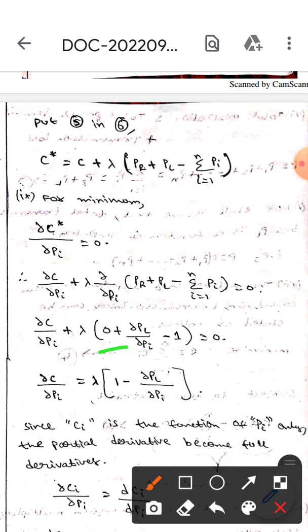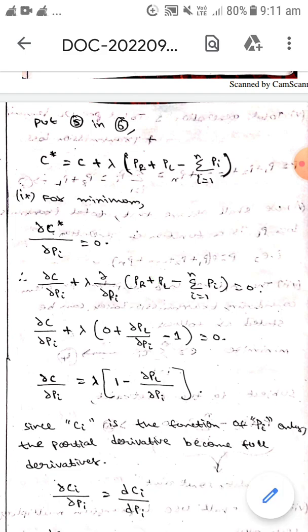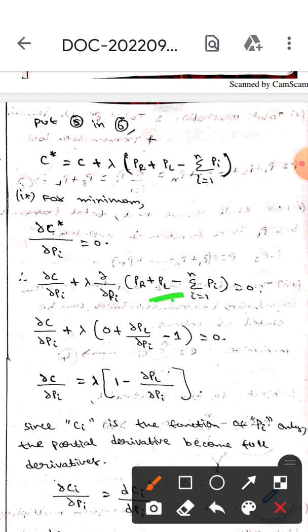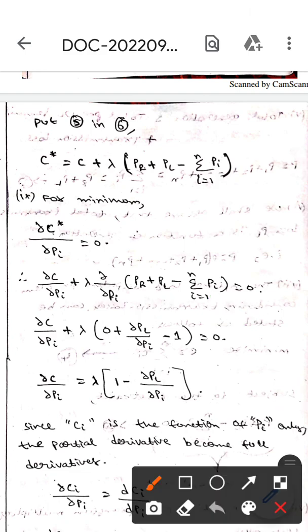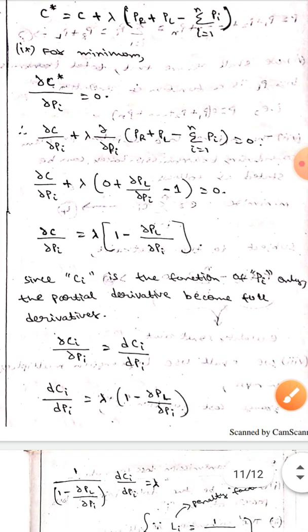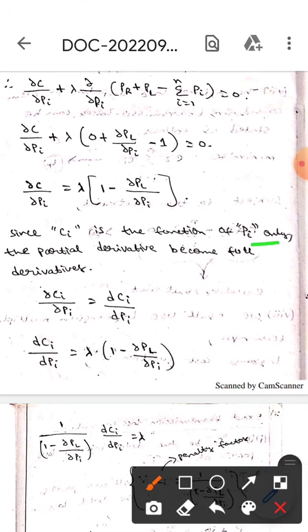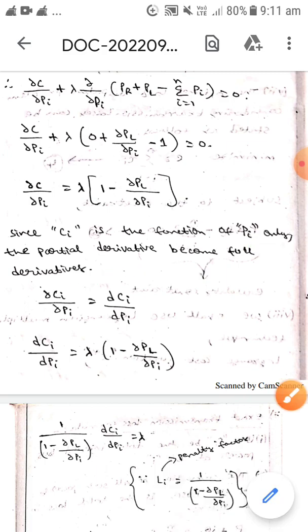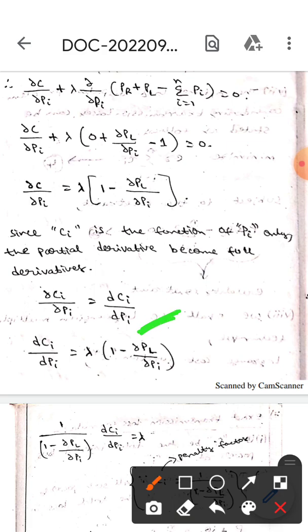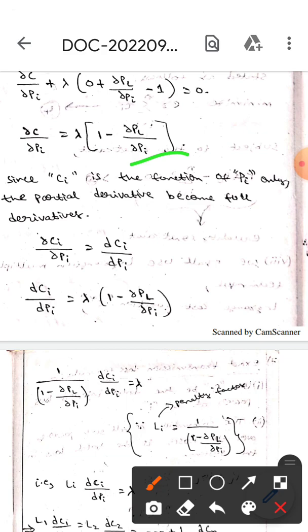Here, PR becomes 0 because it does not depend on Pi, whereas PL depends on Pi so it remains as dou PL by dou Pi. All other terms P1, P2, and so on except Pi become 0 due to differentiation, while Pi differentiates to 1. So we get dou C by dou Pi equals lambda times (1 minus dou PL by dou Pi). Since Ci is a function of Pi only, the partial derivative becomes a full derivative: dou C by dou Pi equals dCi by dPi.